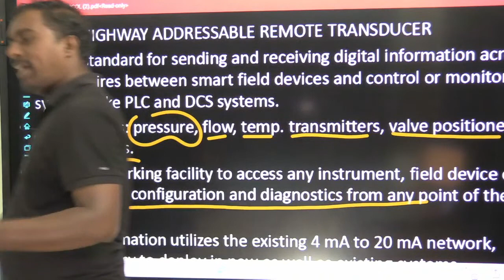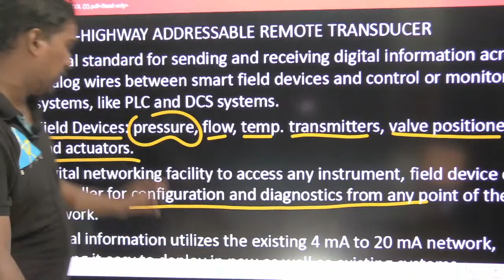This digital networking facility lets you access any instrument, field device, or controller for configuration and diagnostics from any point of the network. That is a beautiful thing. If you use 4 to 20 milliamperes, you have to make proper current wired connections, but here you are configuring the devices. That is what you can also do using a PLC. When you dump the PLC program into the PLC logics, RSLogix, and open the SCADA software, what is happening? You are configuring the RSLogix, you are configuring the devices.